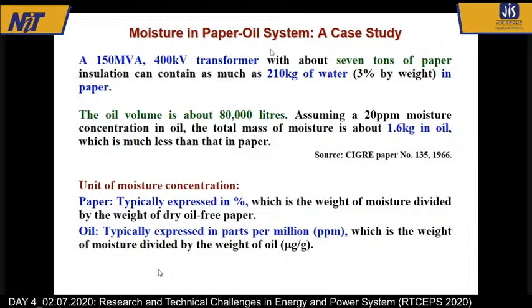But look at that, 210 kilo of water will be in paper and only 1.6 kilo in oil. That's the real situation in a practical transformer. And these 210 kilo of water will further damage the paper insulation. Replacing the 7 tons of paper insulation practically costs half of the transformer cost.